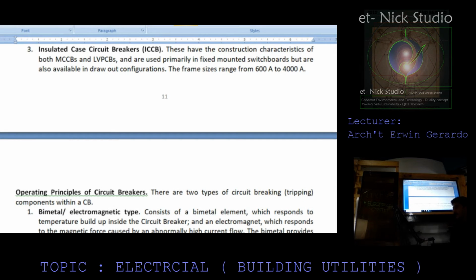Third, insulated case circuit breakers. These have the construction characteristics of both MCCBs and LVPCBs and are used primarily in fixed mounted switchboards but are also available in draw-out configuration. The frame sizes range from 600 ampere to 4000 ampere.